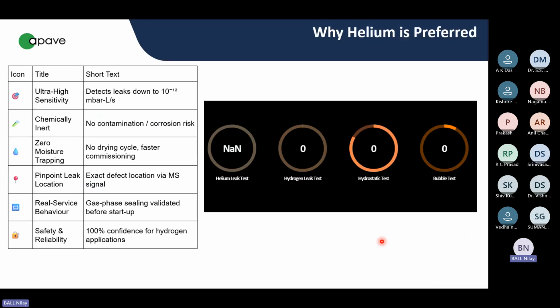Now you can see, by doing a bubble test, you can only catch a fraction of the leakage that can happen. With hydrostatic testing, there's still a big gap that remains open. But with a helium leak test, you can create a zero leakage path and absolutely trap all the leakages that can happen.